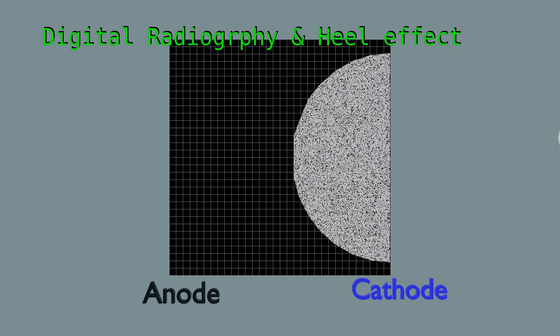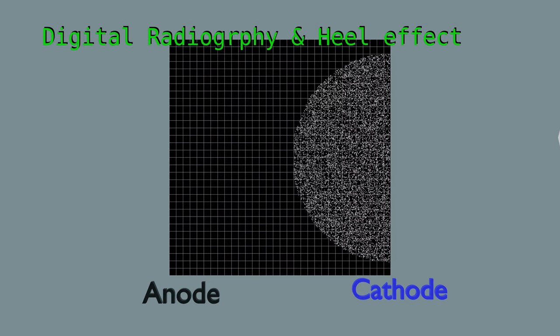With use of computer algorithms, the individual pixel value of a DR detector can be manipulated to produce a final image for a uniform beam. Flat fielding image processing methods are employed to make such corrections.